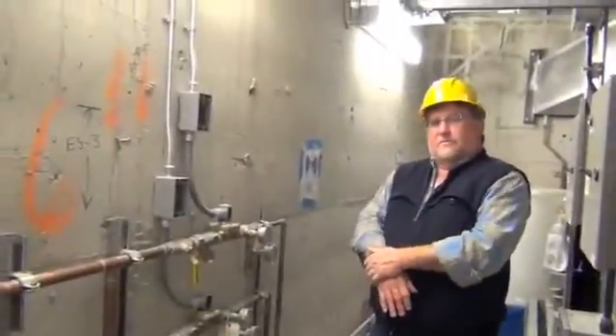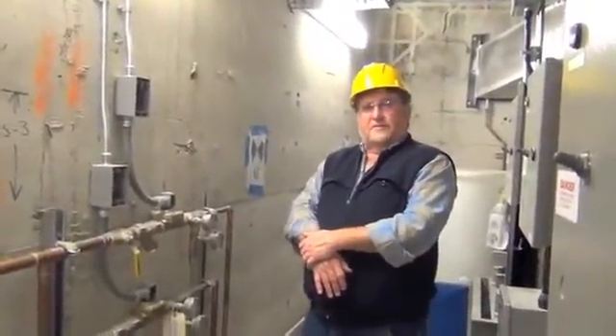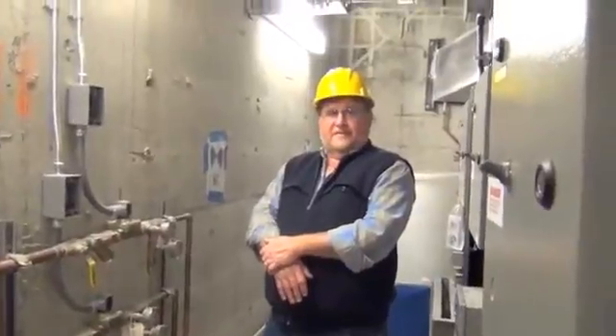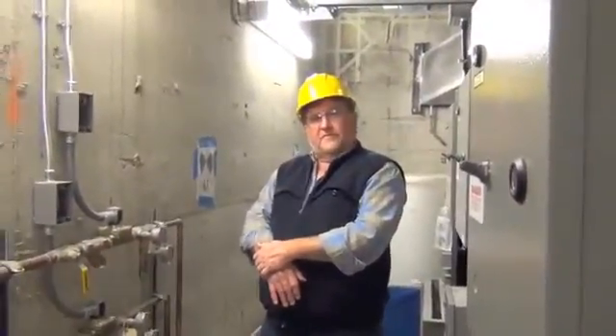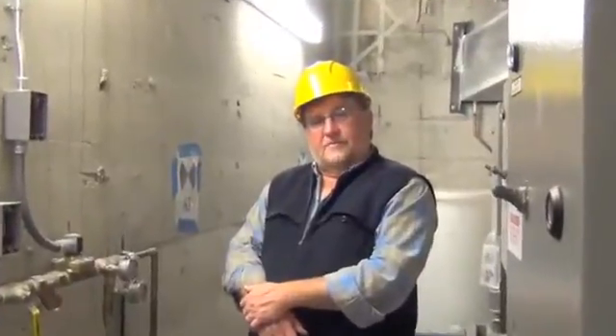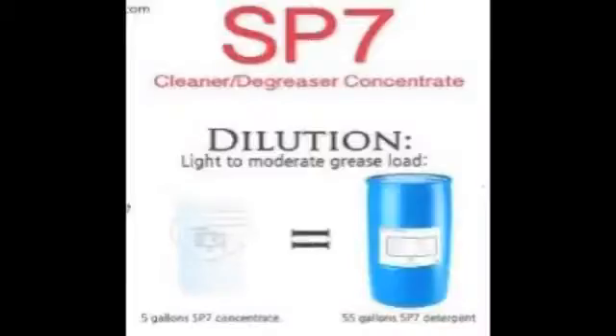The Smog Hog incorporates an automatic wash system which comes on a time basis during the hours of operation in the evening when the restaurant is shut down. It utilizes spray nozzles and hot water with the periodic addition of a proprietary specialized detergent concentrate to clean the accumulated grease and smoke particulate from the precipitator cells, keeping the Smog Hog in operation for many months prior to any required manual exchange of those components.